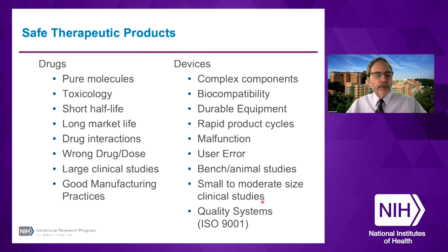In drugs, we're concerned about toxicology, whereas in devices, the issue is biocompatibility. Drugs have a short half-life and a very long market life, whereas devices are durable equipment. It may be an implant that's going to be around for several decades, and they have very rapid product cycles. With drugs, we're concerned about drug interactions and administration of the wrong drug or the wrong dose. In devices, the issue is more a malfunction of the device or user error in its operation.